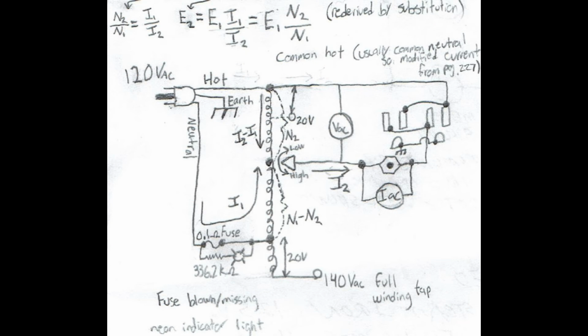To fix this wiring, I'm planning on switching the incoming hot and neutral wires from the line, and also switching the outlet points so that the common terminal is connected to the neutral and the wiper is not on the neutral anymore. We want the wiper to be on the hot part of the load outlet.